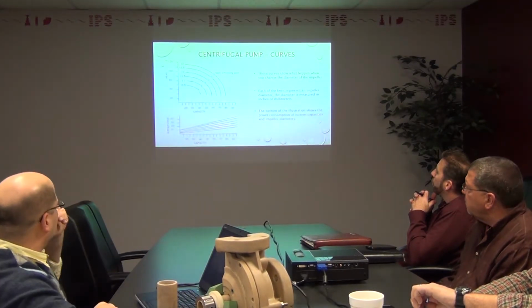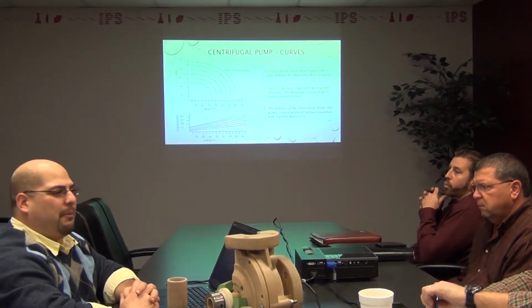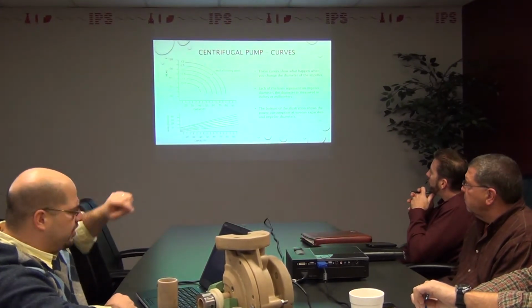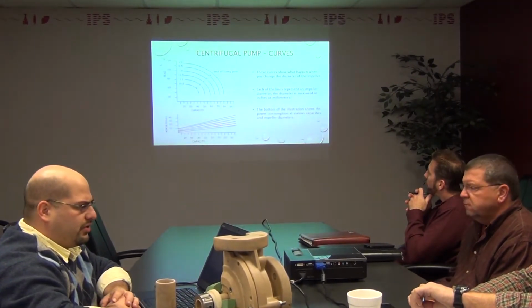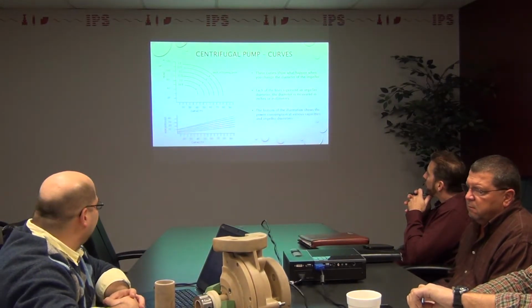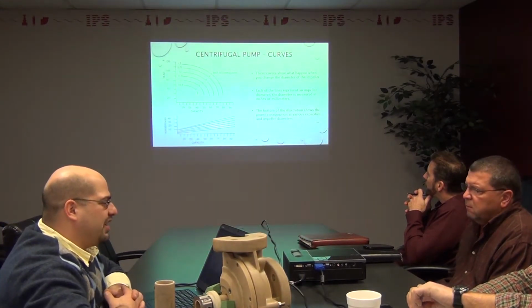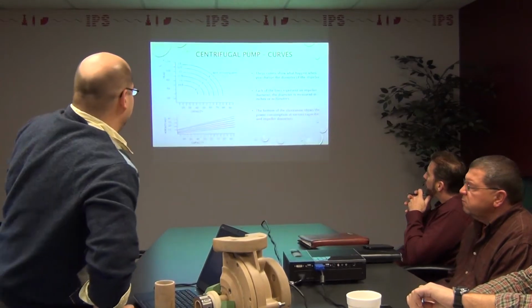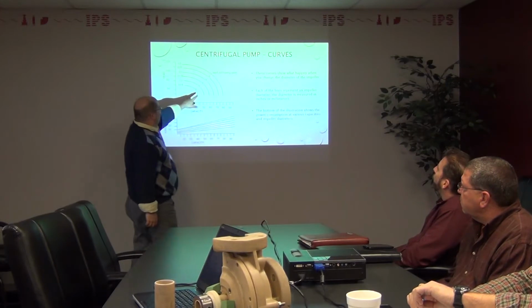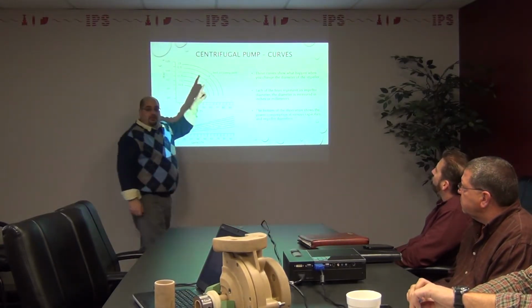Okay, so one of the things that we do to oversize that, the first thing I would take a look at, so he's got an application at that, what did you say? 60 at 80, yeah. Okay. So the first thing that I would do is say, alright, let's try to accomplish this application by going with a max impeller. If I go with that 13-inch impeller, I'm a little too high to what his point is, right? His point's here. If I go with this, I'm way over here, right? I'm not hitting this point.